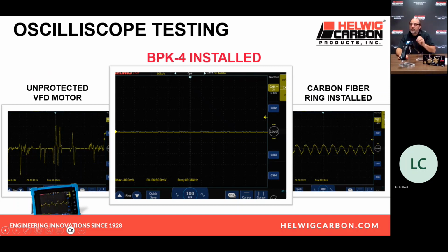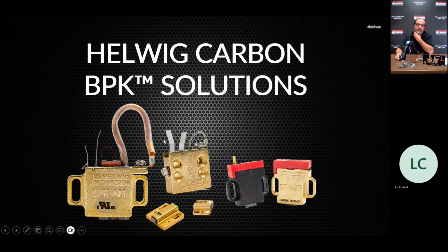And that signal will only deteriorate as time goes by as the force of the fibers decreases. And with our kit installed, because we maintain force with a silver graphite high frequency brush, we expect to see a result that is a dead flat line for the duration, the life of the brush, which is going to be, in most cases, 5, 7 years or beyond, typically.